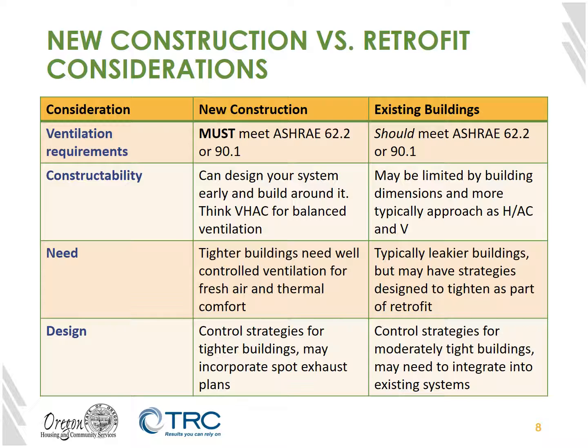Now, existing buildings are typically leakier to start with. And what we really want to think about there is when the building is breathing. If we leave it up to Mother Nature and the forces such as stack effect, warm air rising, and wind effect on buildings, wind blowing and moving air in and out, we're no longer in control of when the building is ventilating. So paying attention to smart, balanced ventilation strategies helps us determine when the building breathes when we update existing buildings, and helps ensure that they breathe at all when we build these tighter new construction buildings.